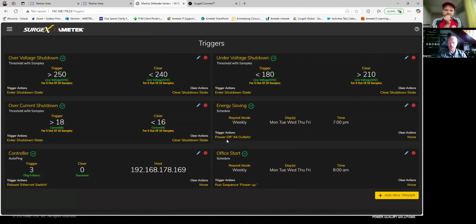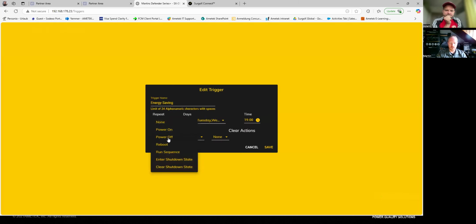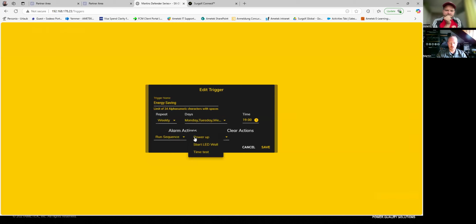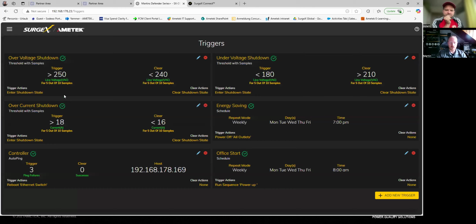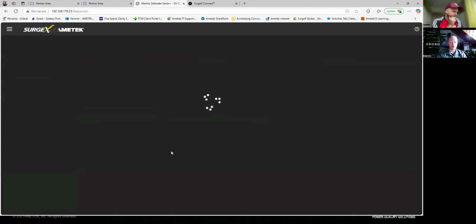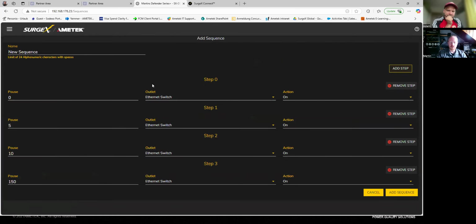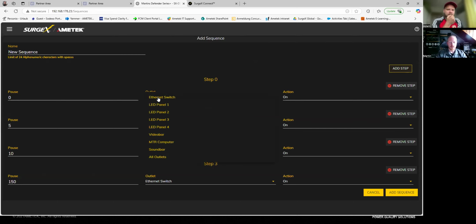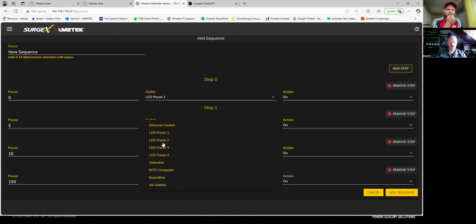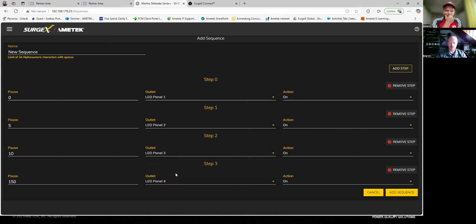For example, with the energy saving trigger, it says power off all outlets now, but I could also just run a sequence, and I need to program that sequence. So what I could do is program a sequence taking into account that the touch panel and the control processor need to keep running. So I can define, okay, I just want to switch on or switch off, for example, just the LED panels.